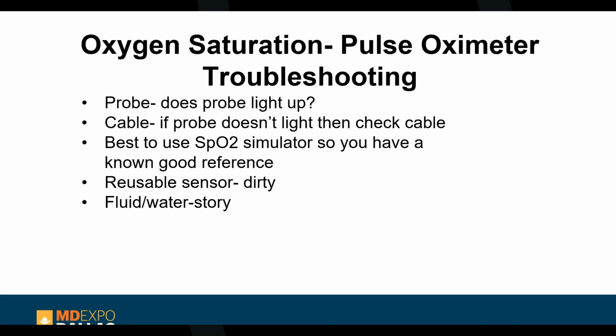When I gave the presentation, the guys that sent me the Welch Allyn thing go to a lot of clinics, and they use reusable finger probes at the clinics. They told me they've seen the reusable probes where the sensor's dirty, so it's not absorbing that light correctly. So cleaning the sensor can lead to better pulse oximetry readings. I work in a hospital and we use the Band-Aid style ones that just peel off, and they change them on the patients fairly often. I'm not really used to seeing the reusable ones.